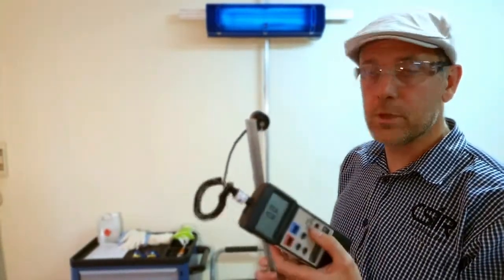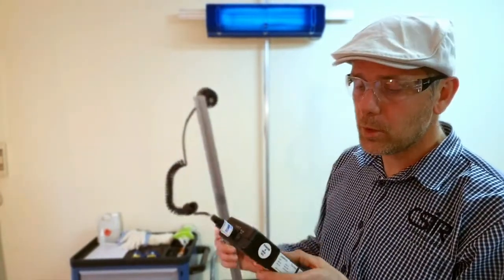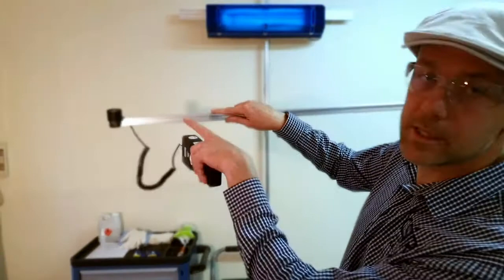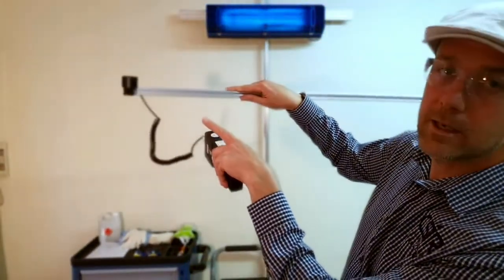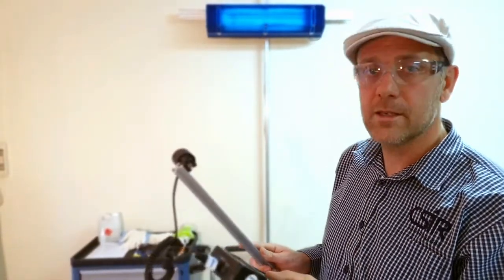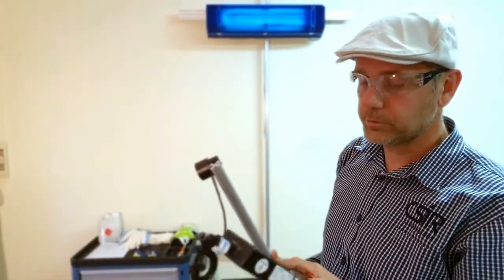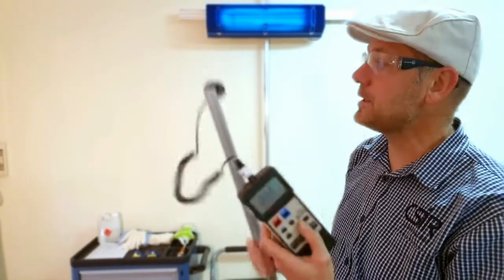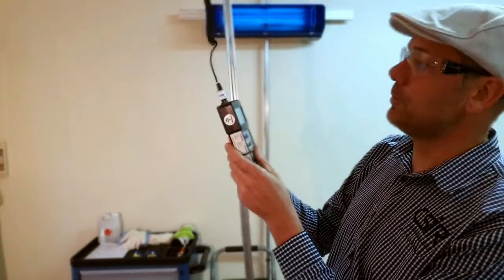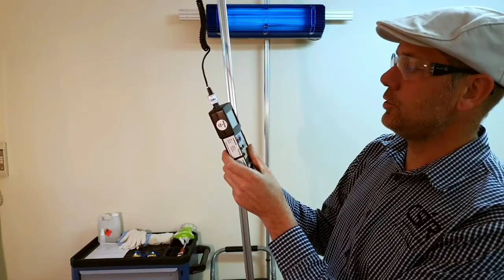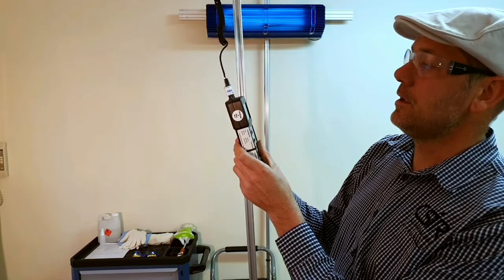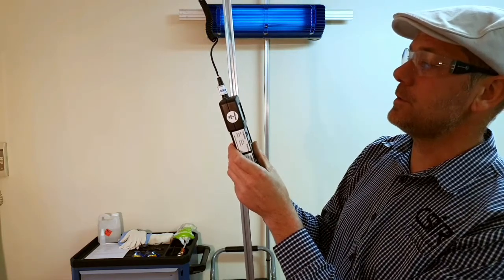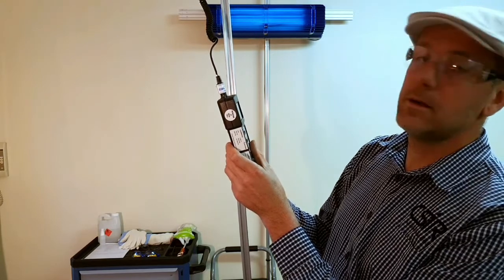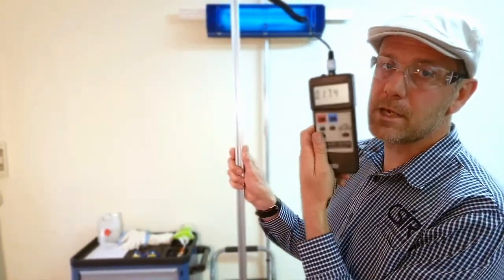All right, then we want to do an upper room measurement. What I have here is my sensor, you'll see, is on a pole. That's 1 meter in length, and I can use that to gauge the distance from the UVGI device so that I know I'm measuring at the right location. Then what we do is select the correct range on the radiometer and lift the sensor up into the upper room. And what we should achieve is a reading of about 250 microwatts per centimeter squared. What I'm achieving at the moment is about 213.